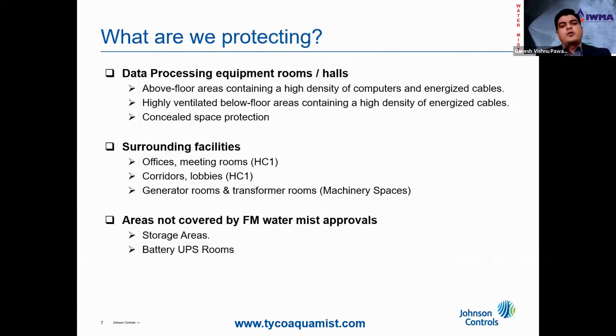So as per FM, what all things can we protect? With the help of water mist, we can protect the data processing equipment rooms, the above floor areas, which contain a high density of computers and energized cables, and the raised floors, which are highly ventilated and also contain a high density of energized cable. And we can also protect the concealed areas. Surrounding facilities such as offices, meeting rooms, corridors, lobbies, generator rooms, and transformer rooms can also be protected with the help of the same water mist kit. Now, please note that FM does not approve water mist for the protection of storage areas and battery UPS rooms.